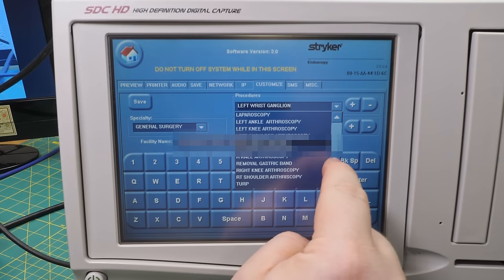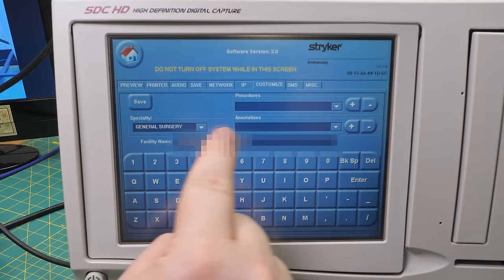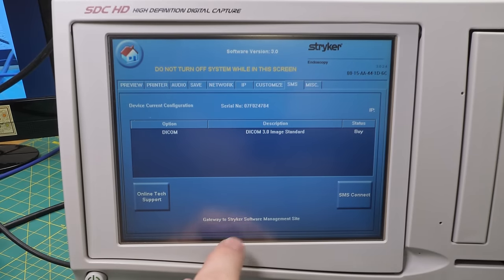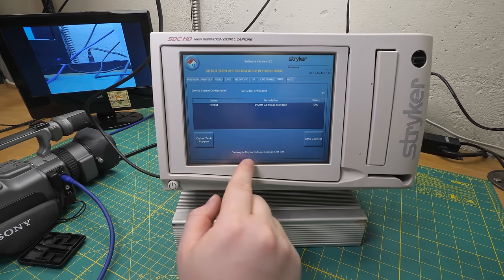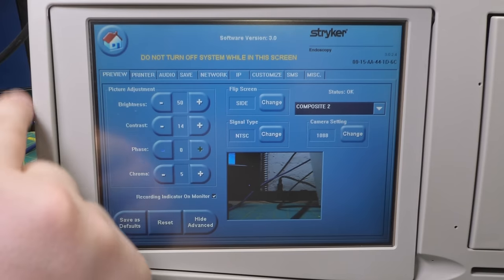This is where we can specify our list of possible procedures and basically determine which department this thing is in. And I guess these are for predetermined annotations - you can just plug in like Mad Libs. I'm guessing this SMS thing - here we go - is the Stryker Software Management Site. I'm going to go ahead and assume this is a license management system. Stryker would have sold you a piece of software you'd install on a server, or they'd sell you a whole server whose only job was to tell devices like this what they're allowed to do. That makes all the difference between a $10,000 device and a $40,000 device. Then we just have date and time and a touchscreen calibrate, which I'm going to stay away from because it's working just fine the way it is.